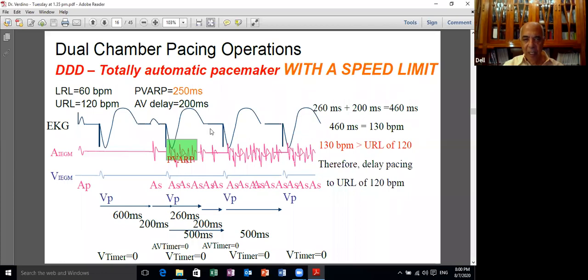But wait a minute. If you have 260 milliseconds, which is the PVARP, and 200 milliseconds, which corresponds to the AV delay, this equals 460 milliseconds. 60,000 divided by 460 milliseconds is 130 beats per minute. But this exceeds the upper rate limit, and the pacemaker cannot violate the upper rate limit. So it has to prolong the PR interval here and delay the conduction to the ventricle more than the AV delay in order to stay within the upper rate limit.